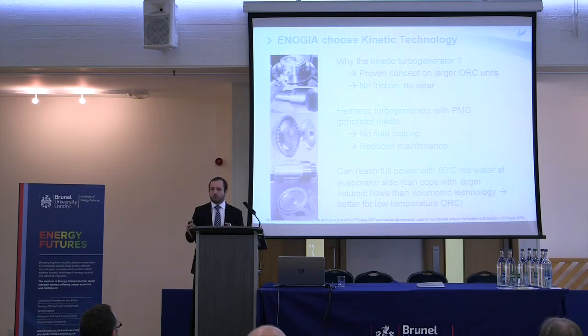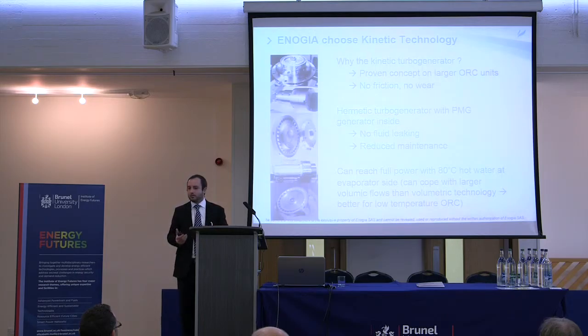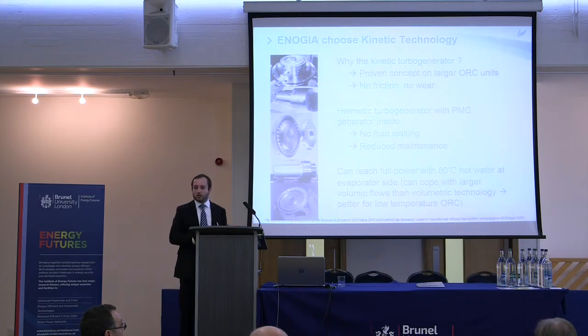In one case, you want to recover all the sensible heat on an open loop, then it's better maybe to use the TFC. In another case, you're on a closed cooling loop, then the ORC could be a better solution if you can work with a return temperature of 70 degrees. Compared to volumetric expanders, the turbine has a very interesting feature: it can reach full power at low temperature because of its high volumetric capacity.